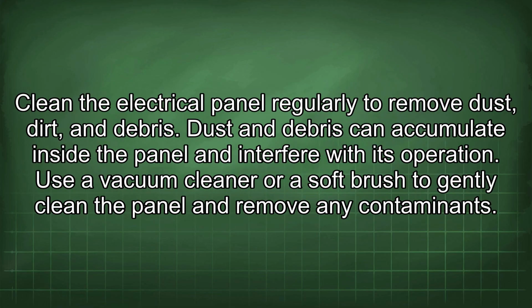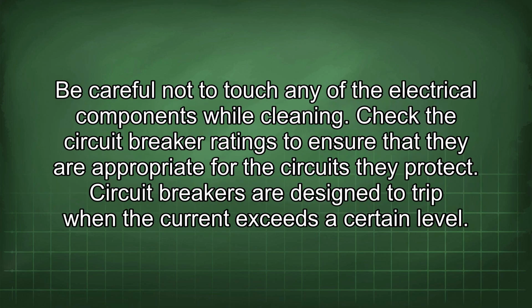Clean the electrical panel regularly to remove dust, dirt, and debris. Dust and debris can accumulate inside the panel and interfere with its operation. Use a vacuum cleaner or a soft brush to gently clean the panel and remove any contaminants. Be careful not to touch any of the electrical components while cleaning.